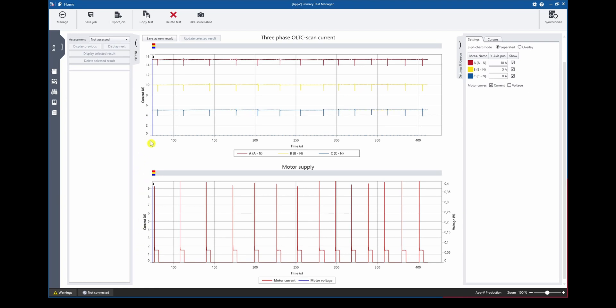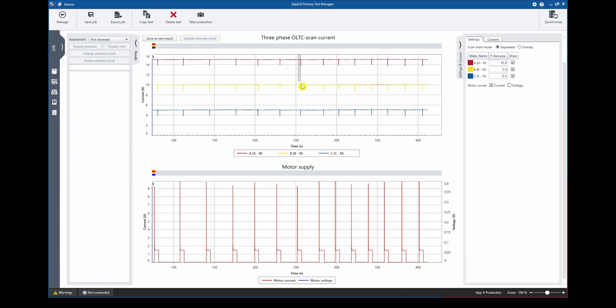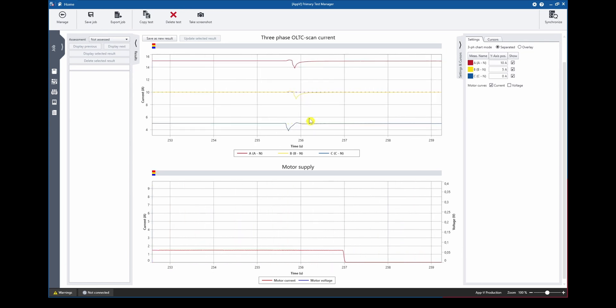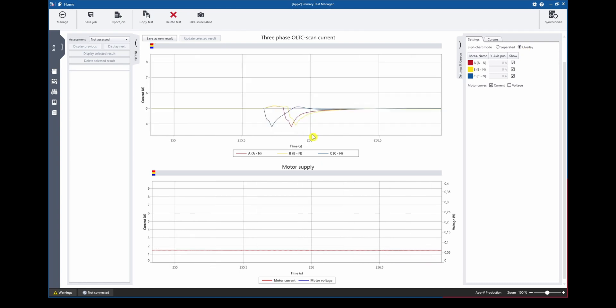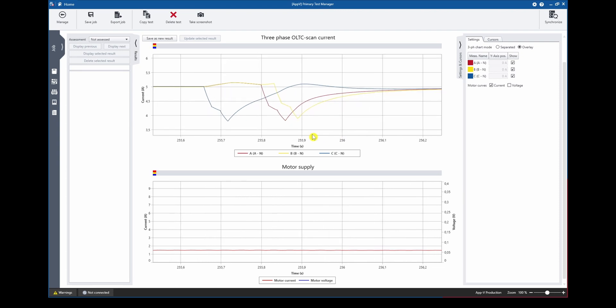First let's focus on the dynamic current curves. As we can see the whole tap switch operation range has been recorded continuously and is depicted in this upper diagram here. So if you were to pick out one of the tap switch operations and zoom in like so we can now see the individual tap switch operations of all three phases in red yellow and blue and now we can also decide to show all three curves as an overlay which means all of them will be depicted on top of each other and if we zoom in we can see there is a slight time shift between the phases and at this point we can make use of our cursors.